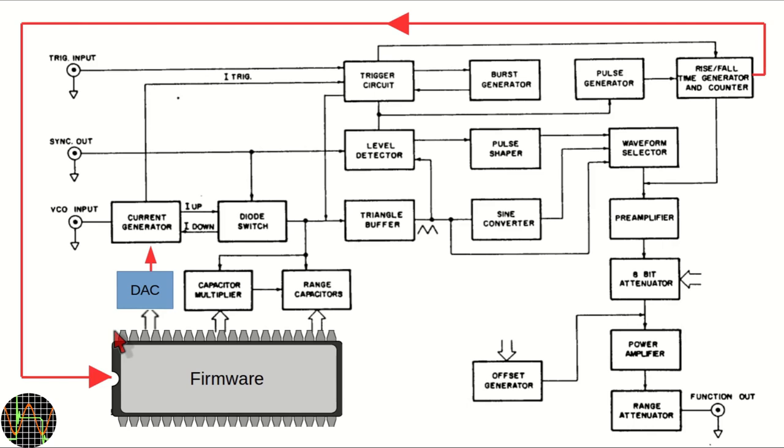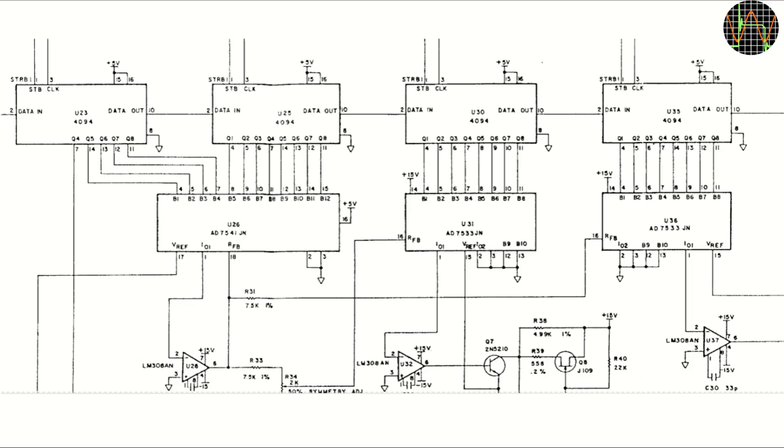Back to my problem. The CPU is happy with the generated 20kHz, but as soon as I select 19.99 it finds that the generated frequency is too far off from the target and displays frequency error to alert to this fact. The fault is therefore either in the DAC or digital to analog converter of the current generator, which seems to work fine for some but not for other frequencies, or in the capacitor selection, picking the wrong or a defective capacitor.